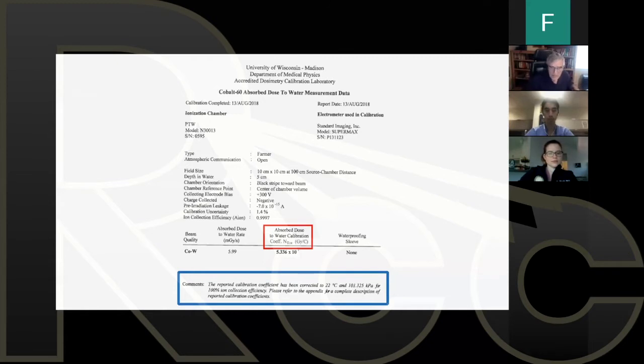Now, also important, highlighted in blue, many mistakes are made because the instrument calibration is referenced to the wrong temperature and pressure. In the bottom of the report there, it says very clearly 22 degrees C and 101.325 kilopascals, which is 760 millimeters of mercury. That's the number that I like to use. So all the instruments are calibrated to nominal standard temperature and pressure. Very important number. Every 2 years, your instrument should be calibrated.